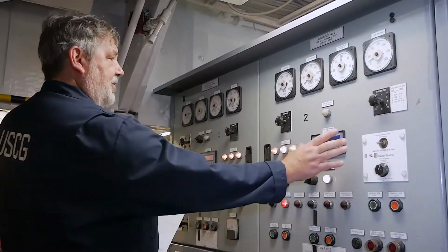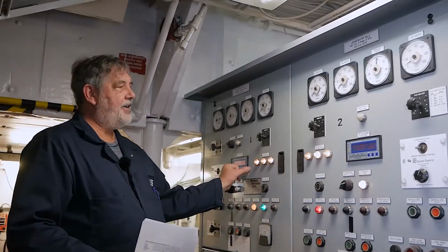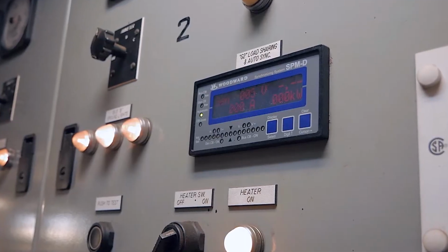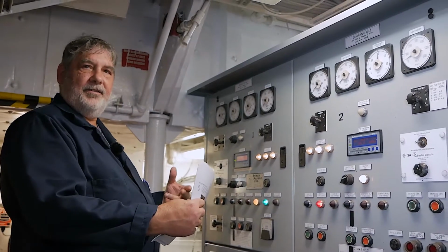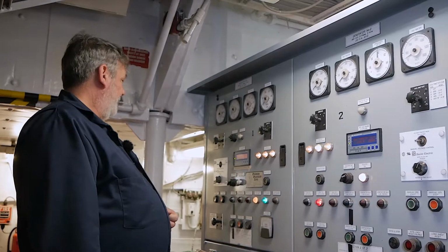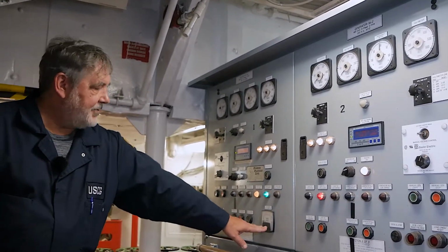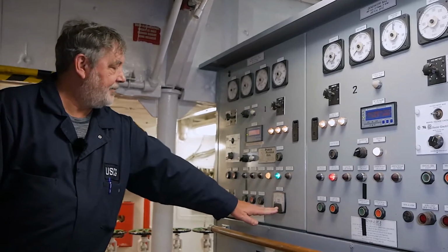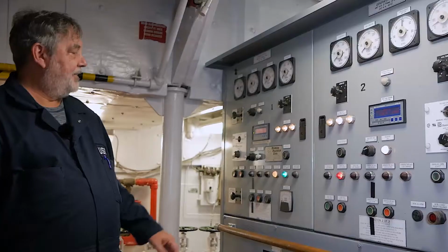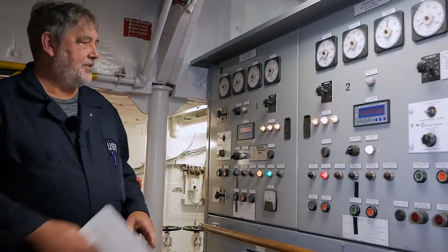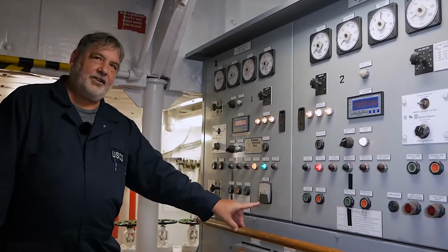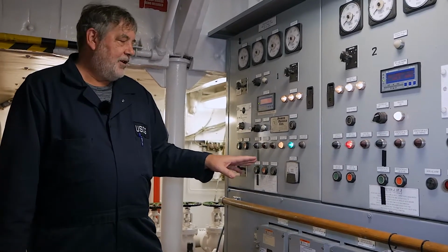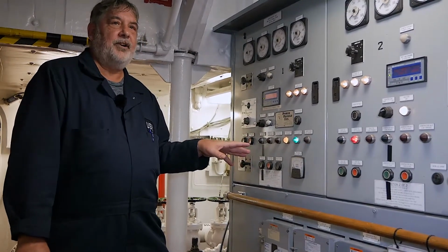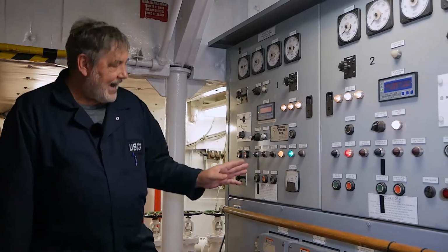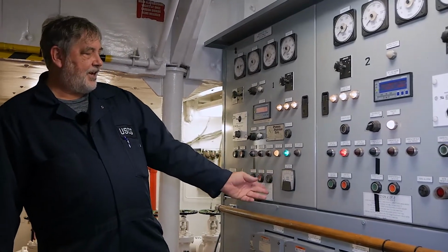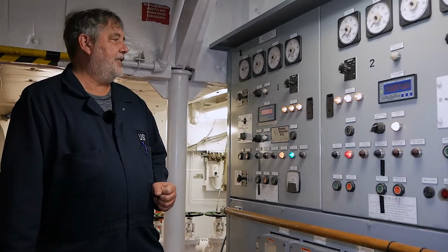right here. This digital display for here and here are going to be your governor controllers for paralleling the generators together. We have 2 types of ground detectors. We have an active ground detector and passive ground detectors. An active ground detector is termed active because it is always indicating whether a ground exists or not. I can look at this meter and it's telling me how many amps are flowing to ground currently.